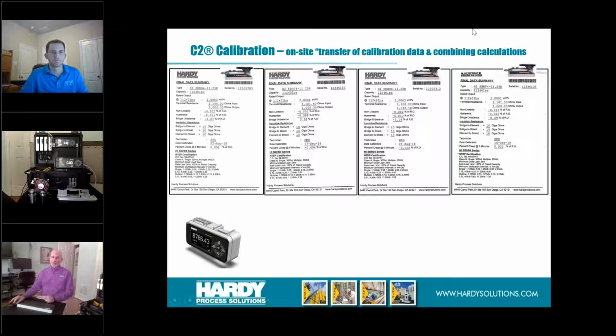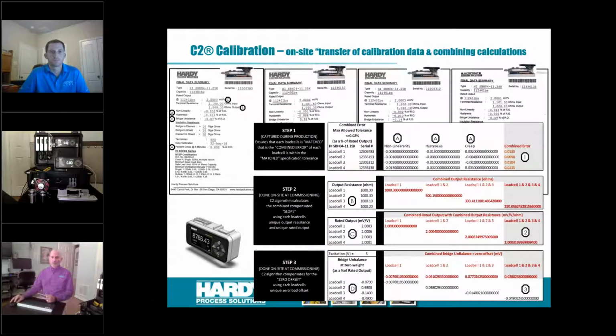So another thing that we can do in the smart calibration that's typically not done in a traditional calibration or in the setup of the scale is that each load cell comes with a data sheet with all this information. In a smart calibration system, all this information is captured. All of the calibration information that I showed you on the previous slide is captured. All that information is loaded onto a memory chip and it's embedded inside the load cell itself. So when the controller hooks up to the load cell, it now has all of this information. It has the slope of that particular load cell with all the errors that were calculated. And there are 3 steps to this process.